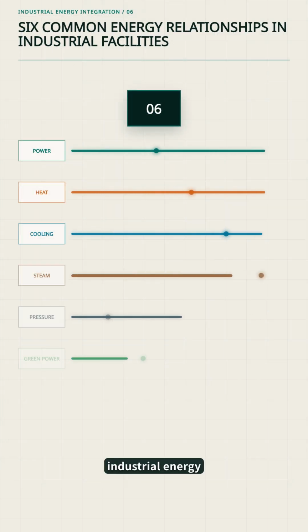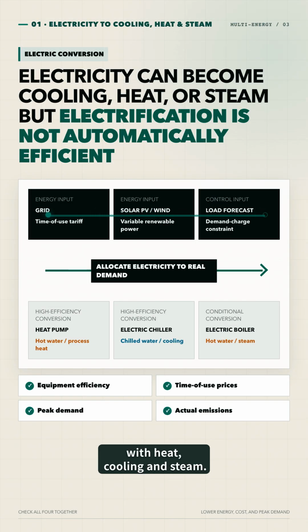Most practical industrial energy integration projects fall into 6 types. The first type connects electricity with heat, cooling, and steam. Heat pump converts electricity into hot water or low-temperature process heat. An electric chiller converts electricity into cooling. Electric and electrode boilers can produce hot water or steam. Solar and wind generation can also be directed first to flexible loads such as heat pumps, chillers, air compressors, and nitrogen generators. But electrification is not automatically energy efficient. Equipment efficiency, time of use tariffs, maximum demand, grid capacity, and the actual carbon factor must all be compared. Otherwise, final energy use may fall while the electricity bill and the facility peak both rise.